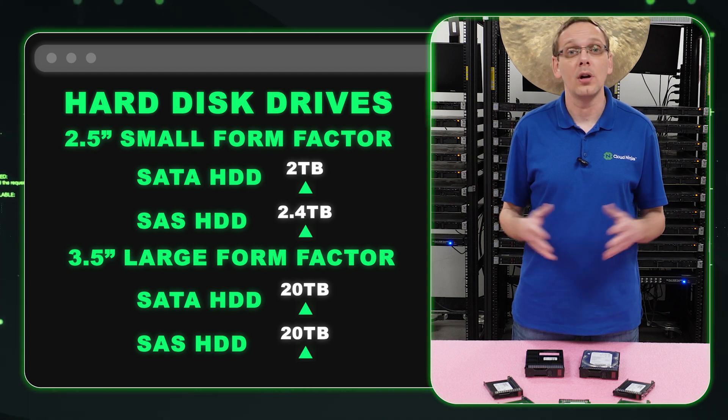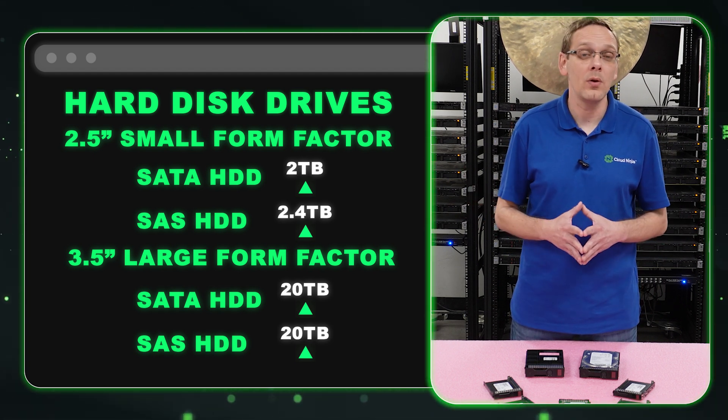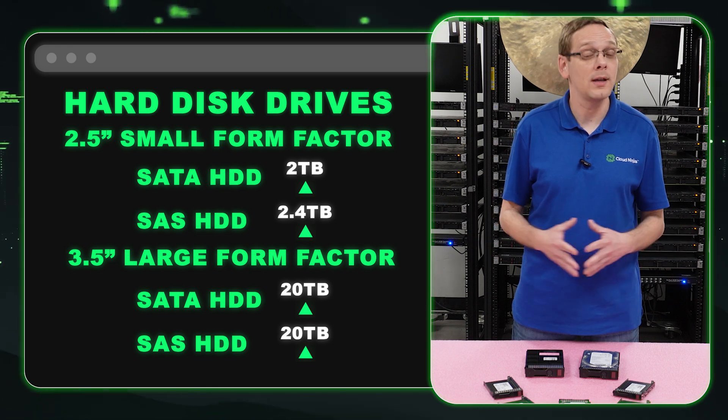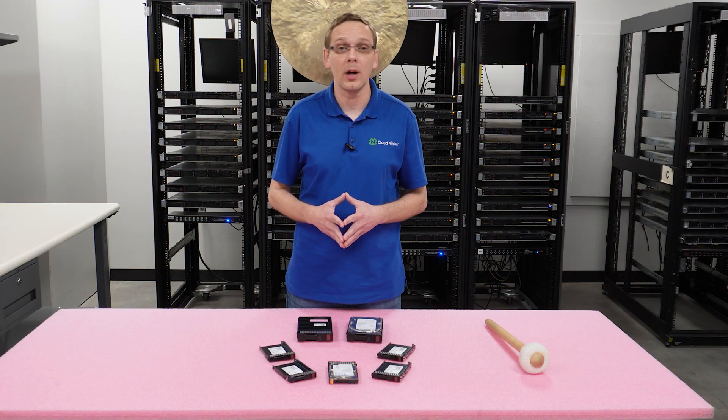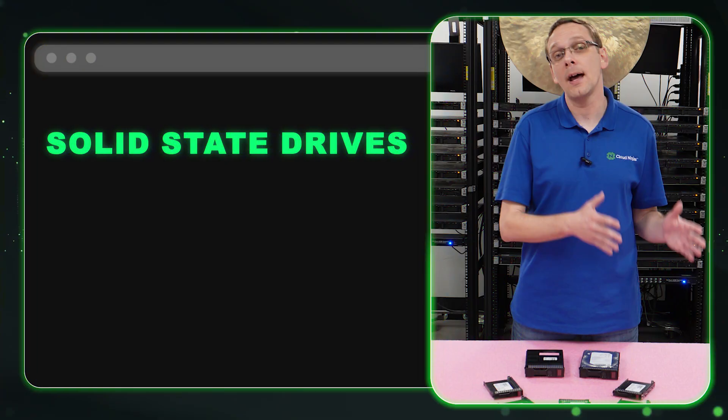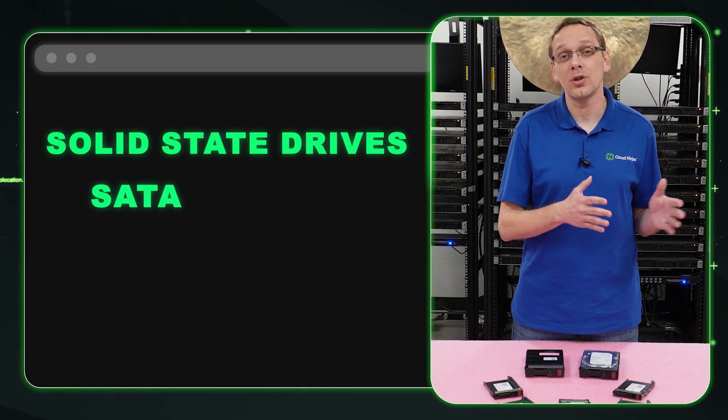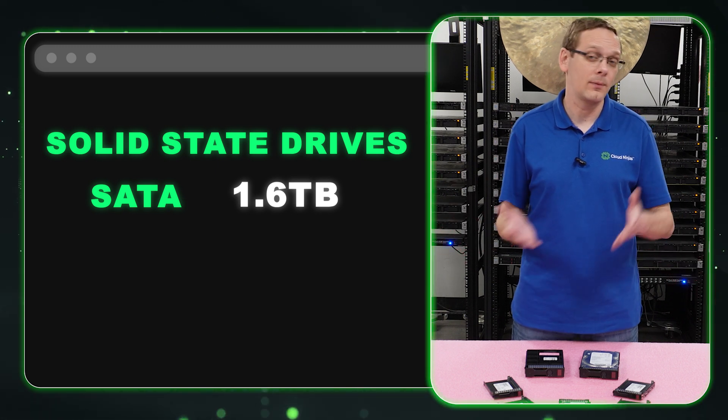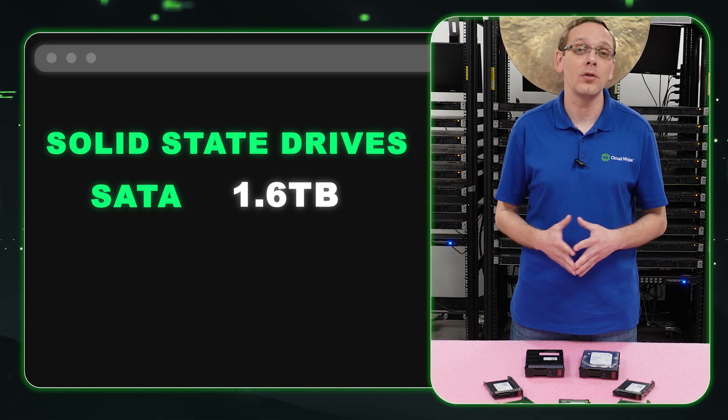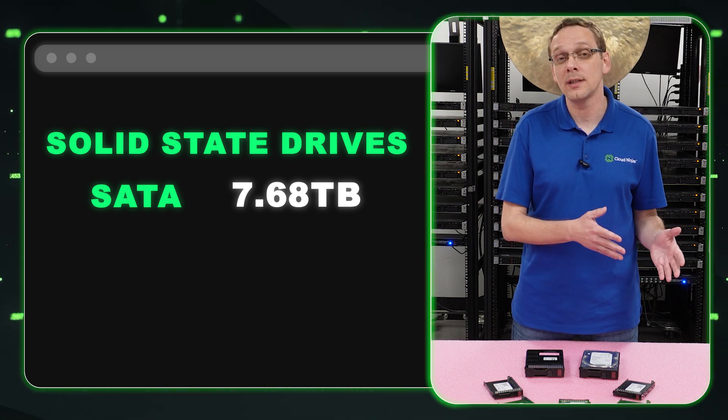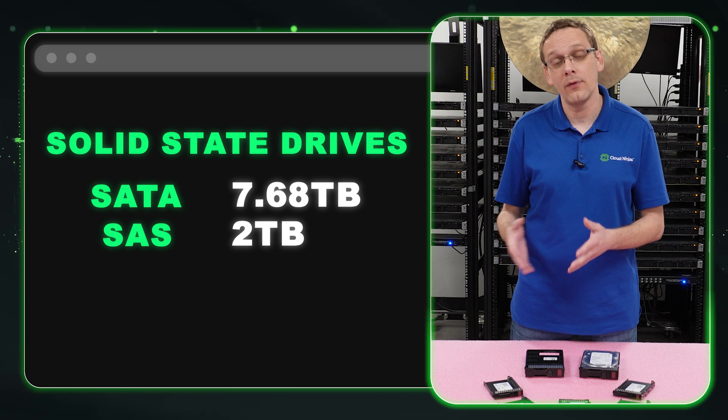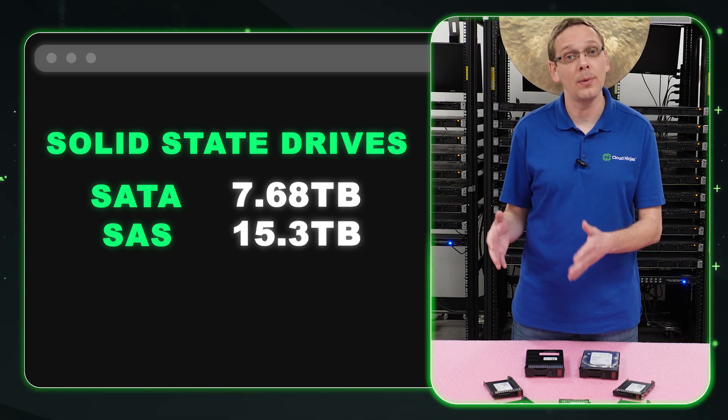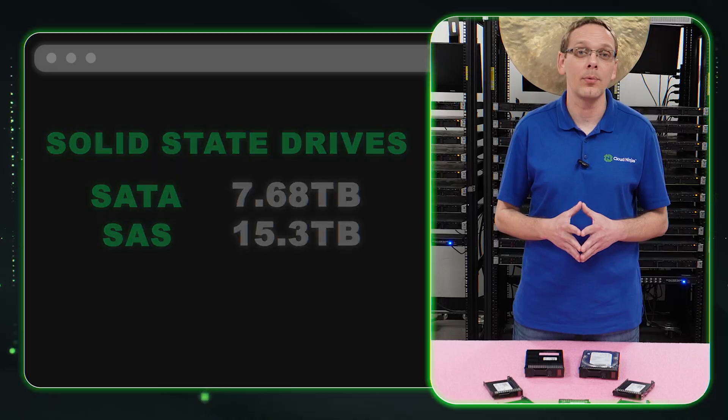That's older information on the spec sheet. That was one reason we wanted to do this video, even though this is an older system, to let people know that yes, you can go off spec and put in larger drives overall. What about solid state drives? For a SATA solid state drive, HPE spec sheet only shows 1.6 terabytes. That's definitely not accurate. Maybe back in the day it was, but right now you can put in 7.68 terabytes. For SAS, it shows only 2 terabytes for a SAS solid state drive. We've put in 15.3. So yes, you can definitely go much higher overall. And again, NVMe isn't compatible.